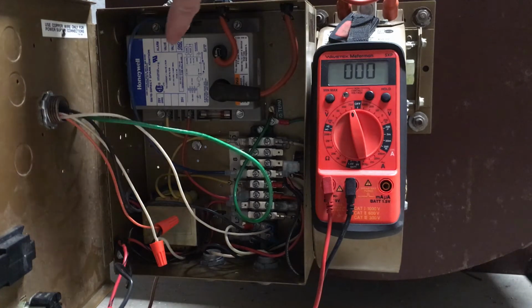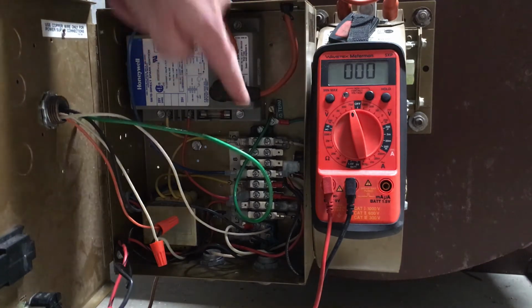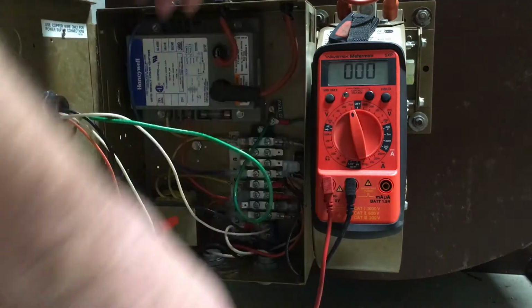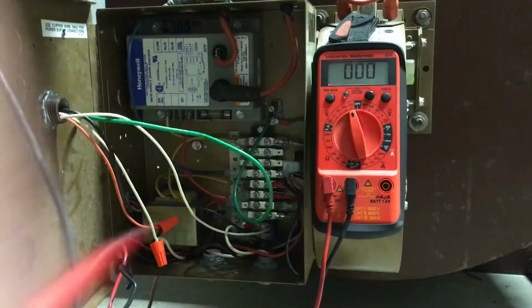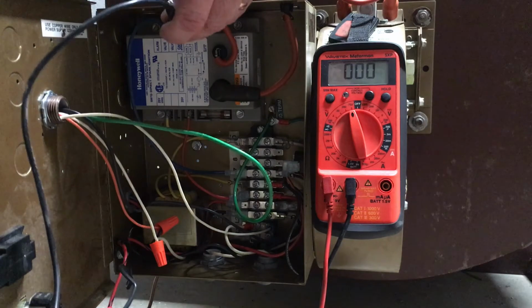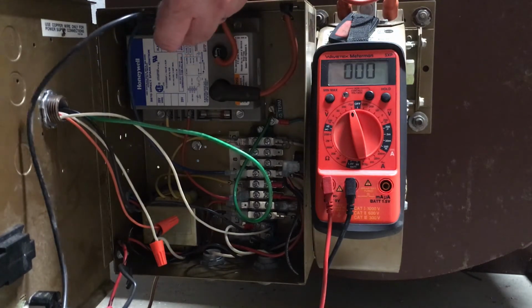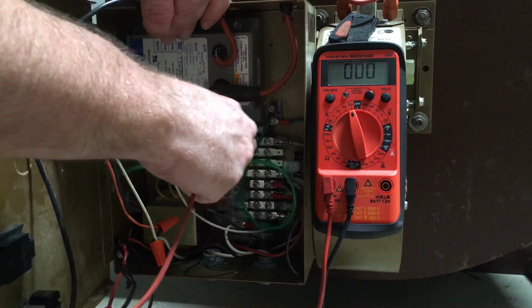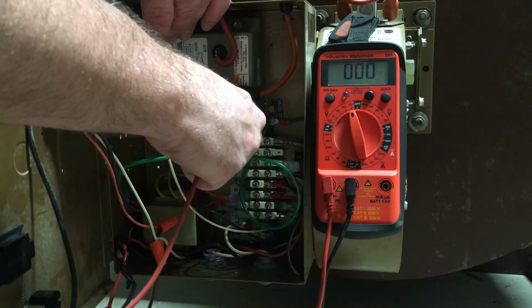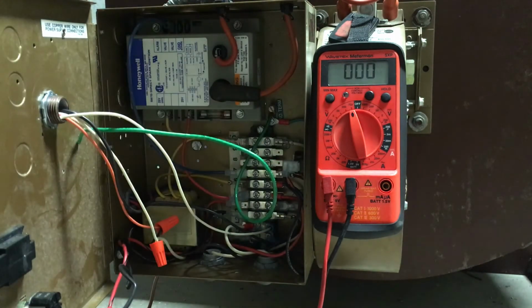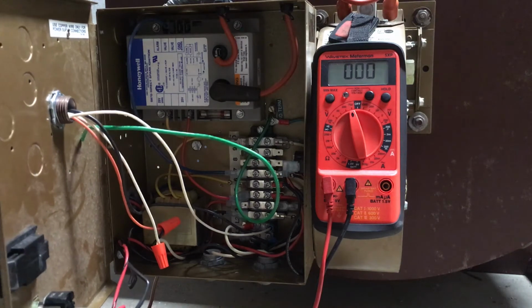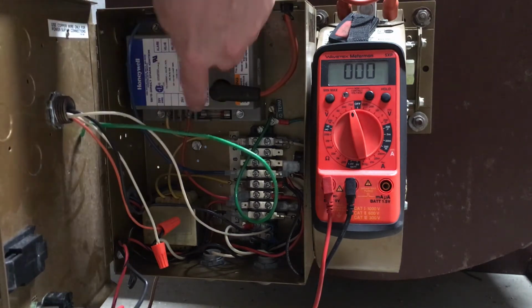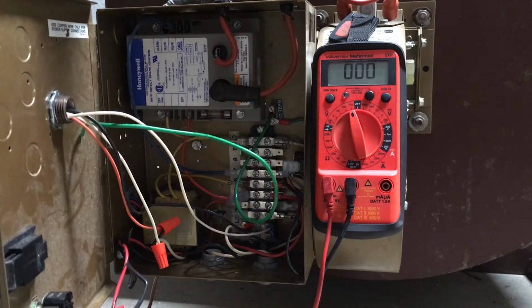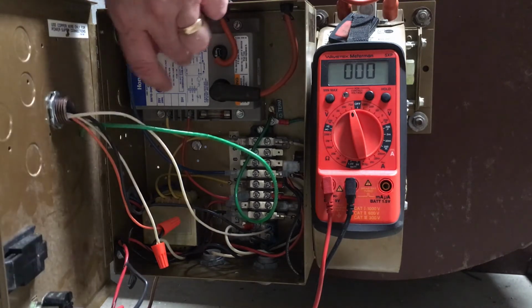So we want to check 24 volt from the valve terminal and terminal 10. As you see, there are two terminals for the valve. Hook up to one of those, and 10. We do not have any voltage. So we need to verify if there's an issue with this. It could be a fuse. There is a fuse on this, so verify that the fuse is working properly. If not, please replace it, and that typically would be the issue if this does not work.